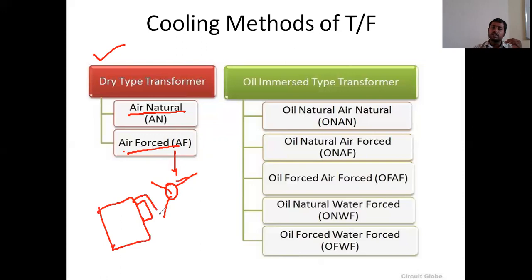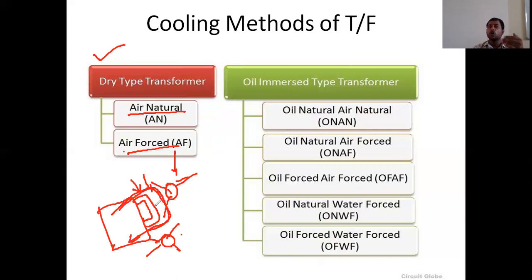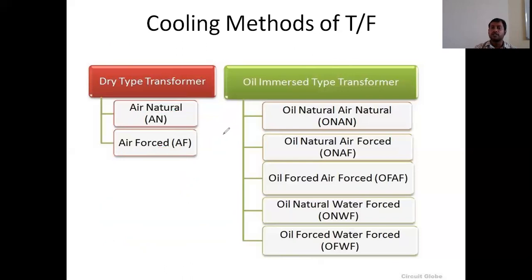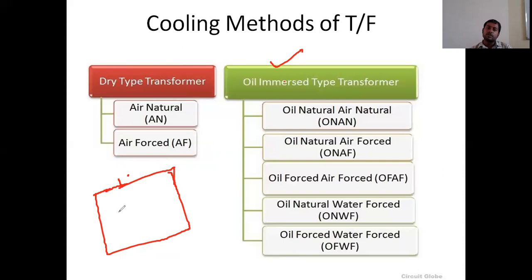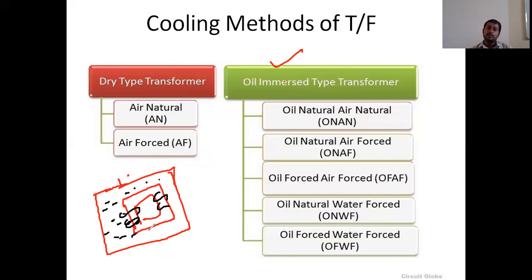This is the transformer and these are the radiators — the outside pipes are nothing but radiators. We use forceful fans to circulate air in the radiators. The oil flowing in the radiators will be cooled by using forced air. That is why this system is called air forced cooling system. The transformer tank contains the core and winding, and when the core and winding are placed in oil, such a system is called oil immersed type transformer.